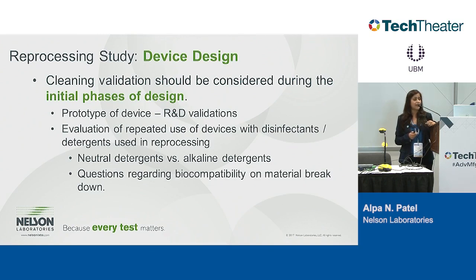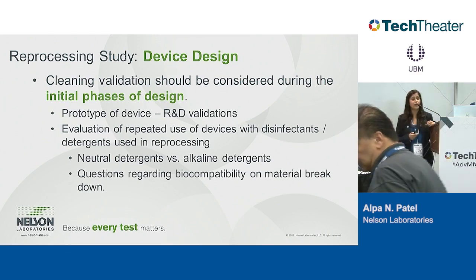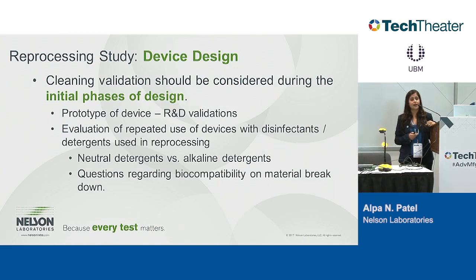Also, questions regarding biocompatibility and material breakdown have been raised by the FDA to many manufacturers: how do you know that after 50 times the material does not affect the patient? This is something we're seeing recently being asked by the FDA, so we do repeat cycles and then do biocompatibility testing at the end of those 50 cycles, or after the 10 cycles, depending on the use of your product.